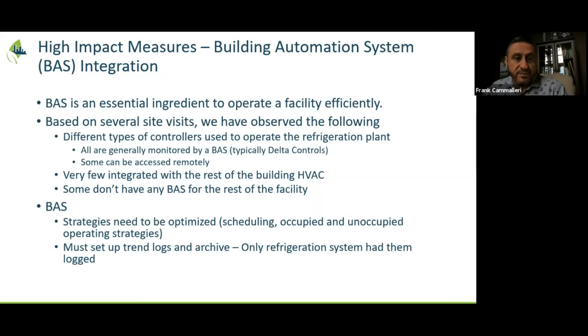Based on our site visits, we typically find some sort of controllers that control the actual refrigeration system. Since most of the systems to date have been serviced by the same vendor, they'll typically have a building automation system front end that helps review and navigate the refrigeration system, but the controllers themselves actually do the controlling. Most of them can be accessed remotely, which is good—if there's a problem, someone can call from their office, or a technician can reach out without having to be physically there to see what's going on.